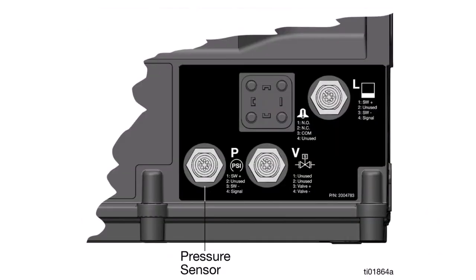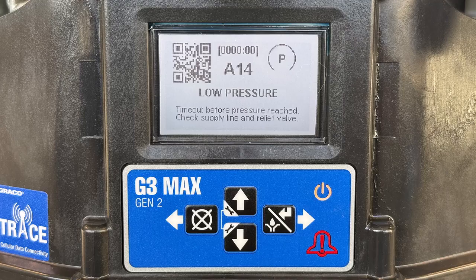The P pressure input is connected to a pressure sensor, either a switch or a transducer, which allows the pump to know when to stop pumping. There are multiple possible causes of a low pressure alarm, and this video will attempt to cover the most common ones as briefly as possible.